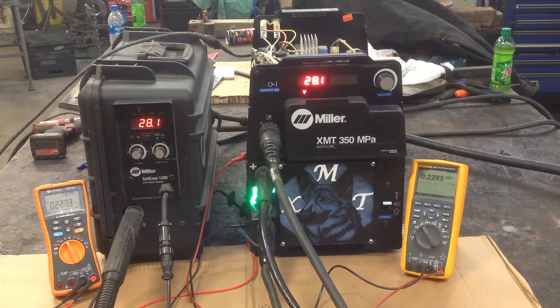Looking at the feedback, you can see that it is compensating maybe a volt, volt and a half. I'm going to do another test — leave it at 28 volts. I put in another 50 feet of cable just on the positive line, so it should have a 150-foot loop and we'll see if it has to compensate any more.